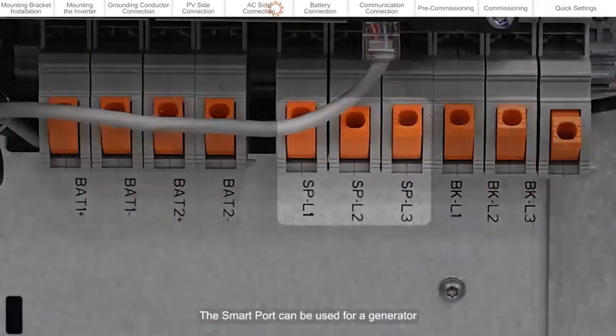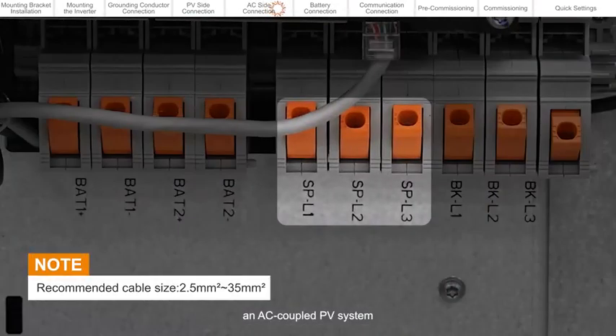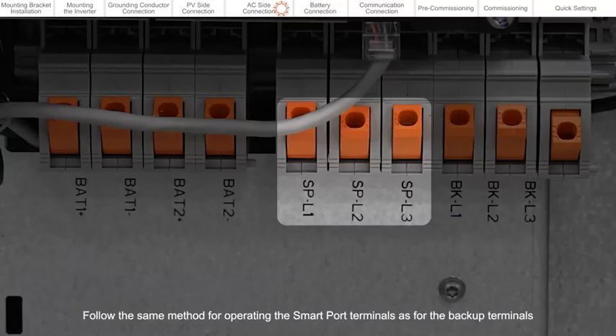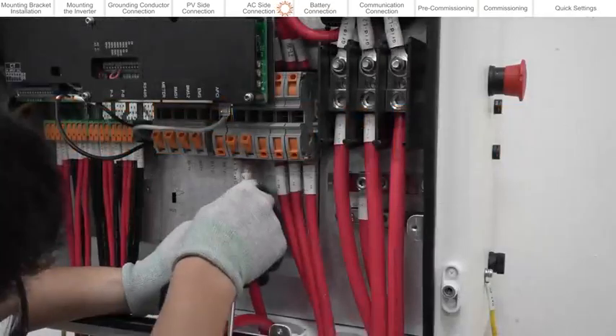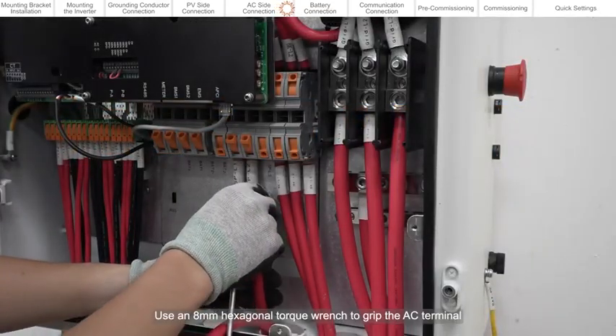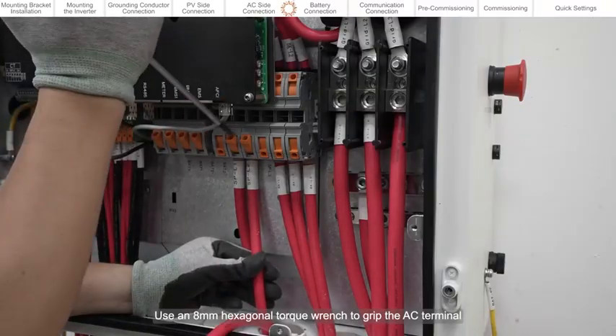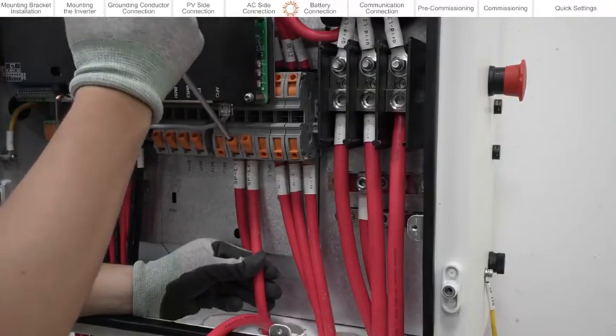The smart port can be used for a generator, an AC-coupled PV system, or for a sheddable load. Follow the same method for operating the smart port terminals as for the backup terminals. Use an 8mm hexagonal torque wrench to grip the AC terminal.